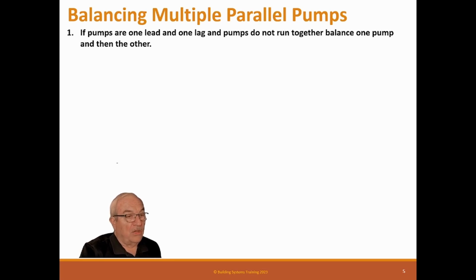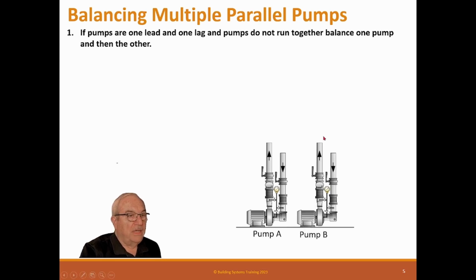The only way to tell that, because the engineer doesn't tell you, is to add up all the coil loads in GPM and see how that matches one pump. If the coil GPM is less than or equal to one pump, then you have a standby pump. If the GPM is a lot more than one pump, then you have staged pumps. So if you have standby pumps, you have 1 and 2, and you know they don't run together, then you just balance one pump and then switch over and balance the other pump. Test one pump against the other to make sure they're the same.